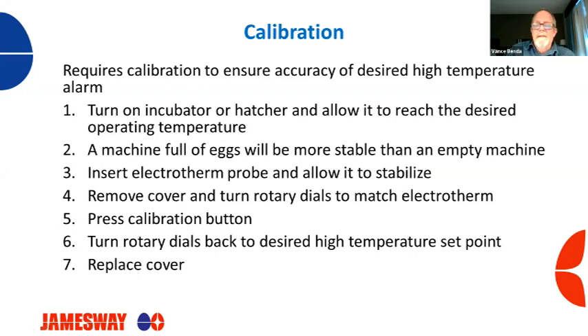It's not stable, and we want to wait till the temperature is stable. As it says in number two here, a machine with eggs is way more stable than an empty machine, and that's what we're looking for, is stable. Another thing that will destabilize your machine while you're trying to do calibration is humidity, because everybody knows humidity has a slight cooling effect. So every time your humidity comes on, your heat's gonna come on to compensate for that cooling effect. So while you're doing calibration, be sure to just disable your humidity.